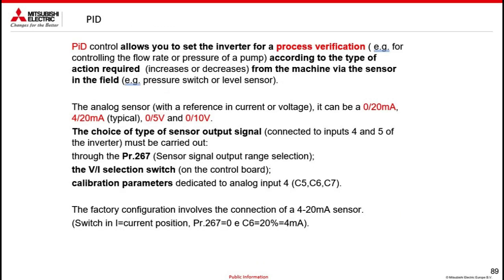Another often used control methodology, which is semi-automatic, is PID control. For example, for a pump, imagine having a pump that must constantly maintain a pressure inside a contact. And so I say to the inverter, you take care of it, you keep the pressure defined by me. This is possible by means of the PID functionality, where by means of an analog signal coming from the field, for example, a pressure transducer, usually it is from 4 to 20 milliampere. To give you an example, I will speak from 0 to 10 volts, because I speak of easy numbers. I will have a pressure transducer that is wired directly to the inverter, which will give me a reading reference.